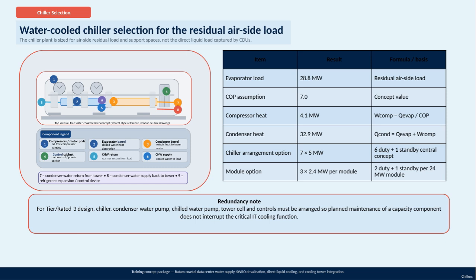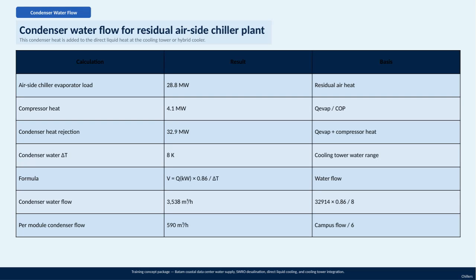warmer water coming back from the load. Finally, condenser water supply and return lines connect back to the cooling tower, and the refrigerant expansion and control device regulate the refrigerant flow. This comprehensive approach ensures efficient, reliable, and maintainable cooling tailored to unique demands of our coastal data center environment. Here we see the condenser water flow for the residual airside chiller plant. The condenser heat generated here is combined with the direct liquid heat at the cooling tower or hybrid cooler, which makes the overall cooling process more efficient.